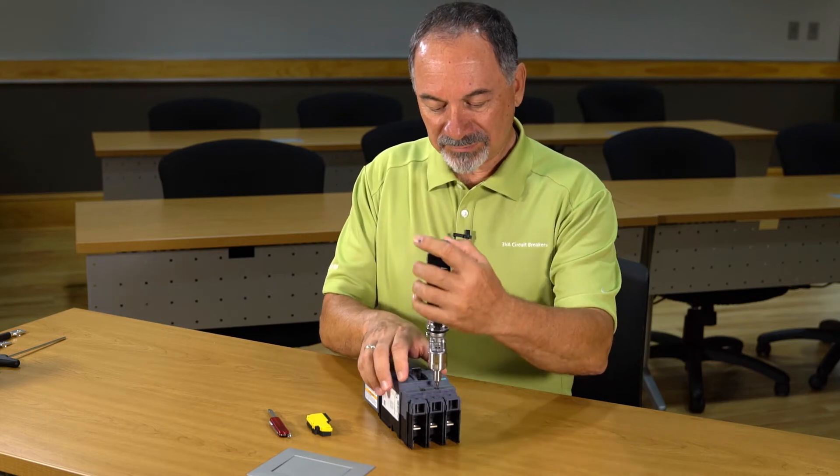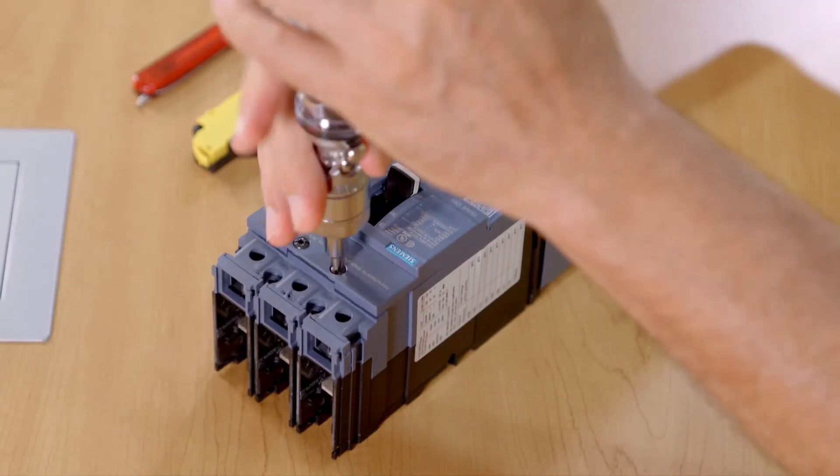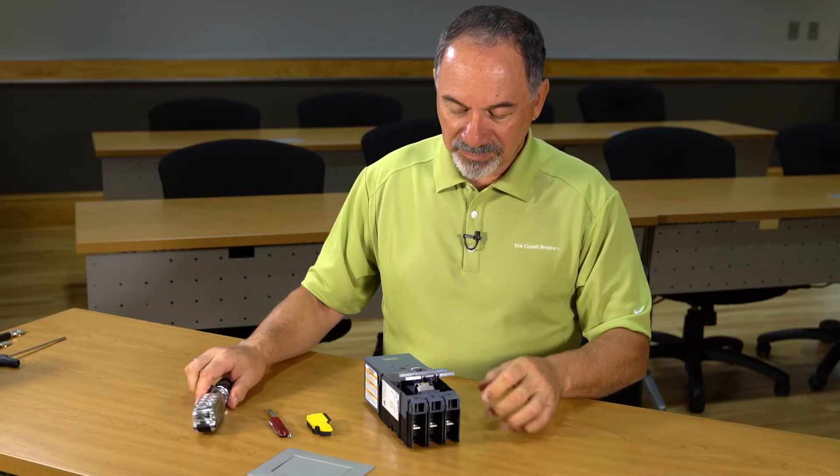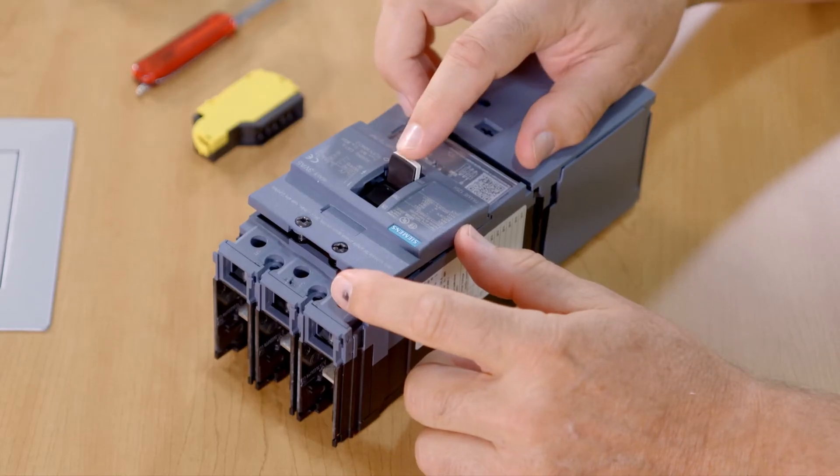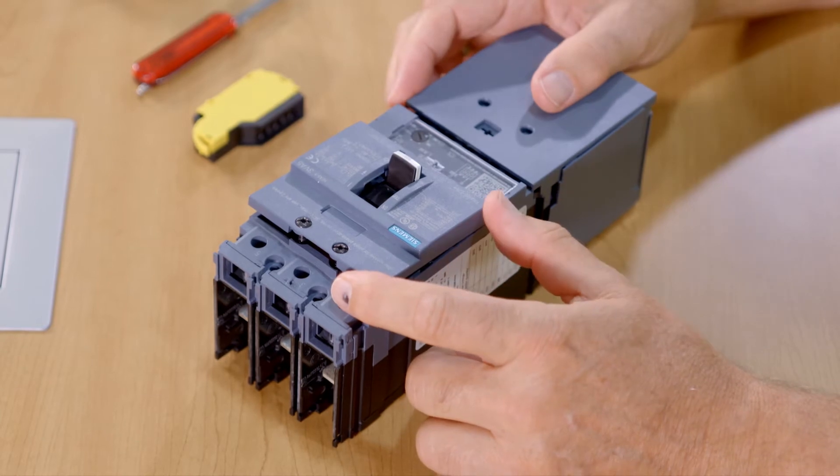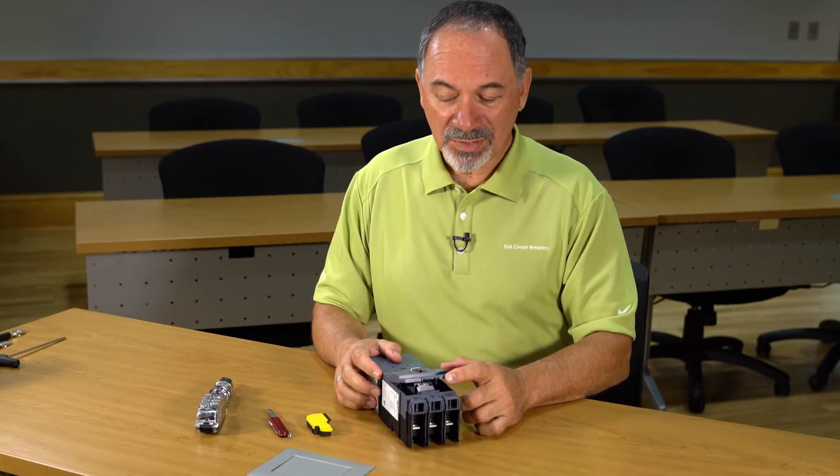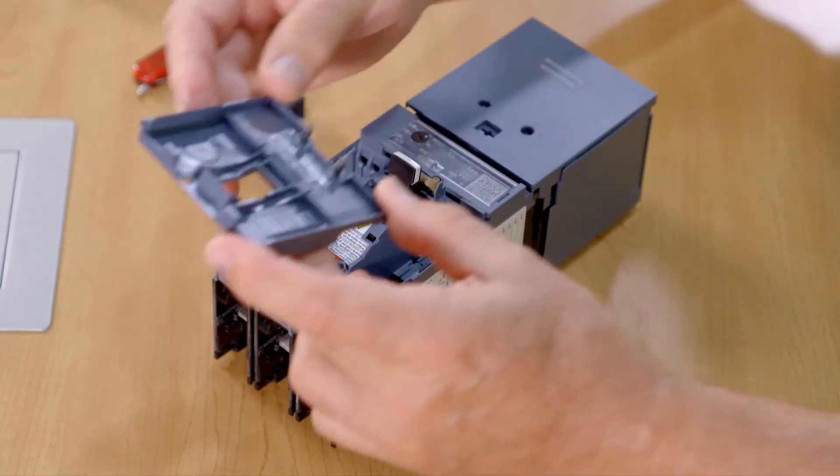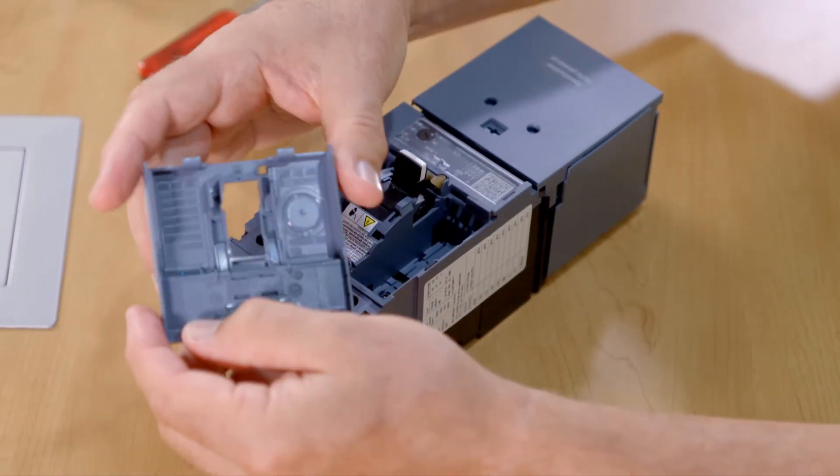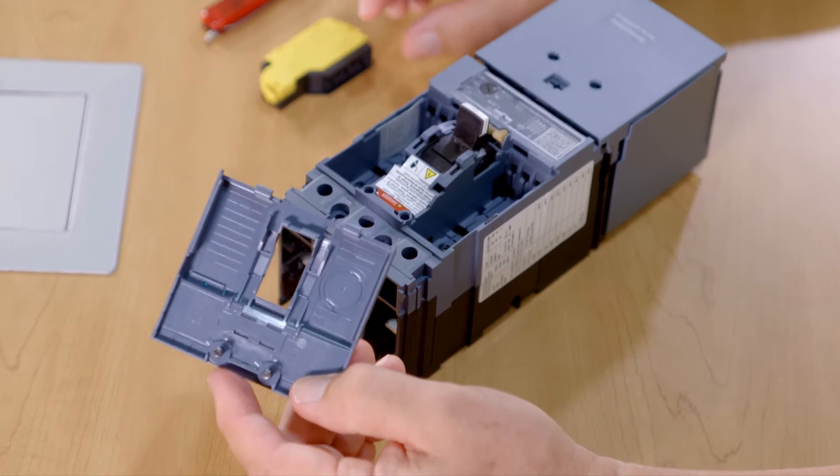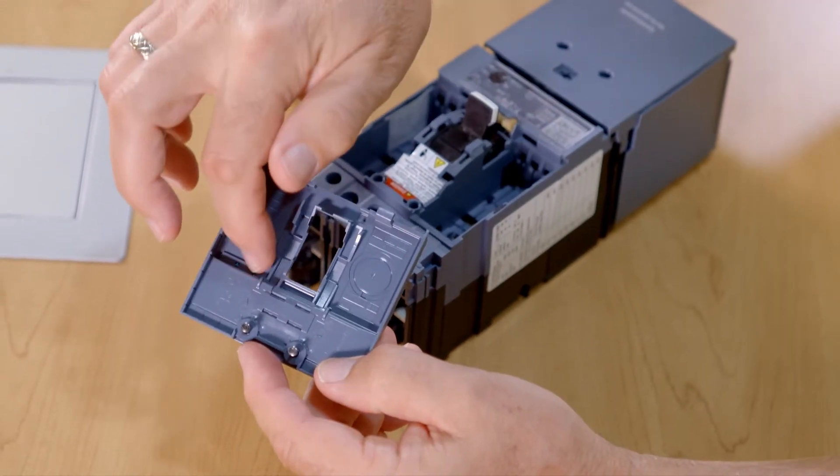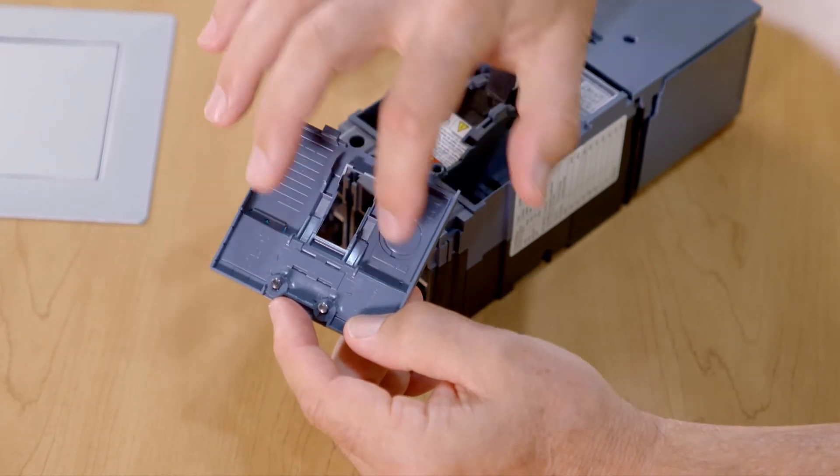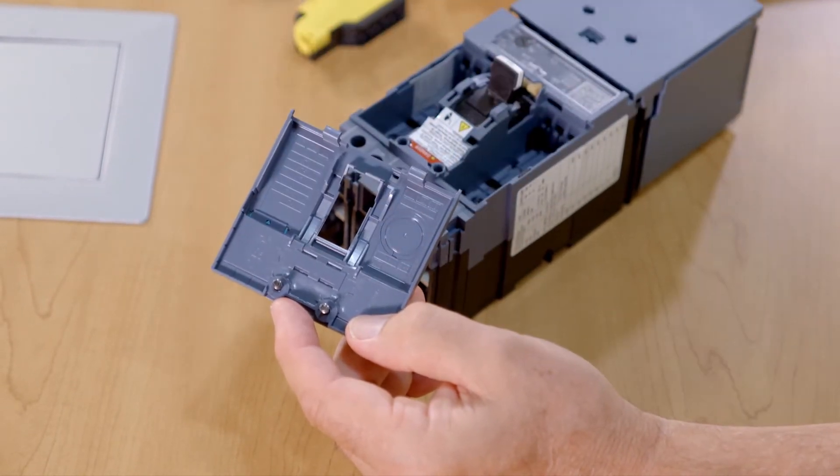First, using a Phillips screwdriver, you remove the accessory cover. Fairly simple. Making sure that the breaker is in the off position. If the breaker is in the trip position or the on position, you cannot remove this cover. When I remove the cover, the first thing I can look at, especially if I throw away the instruction sheets with the box, I can see on the back side of the accessory cover are indicators of where each accessory can be installed.